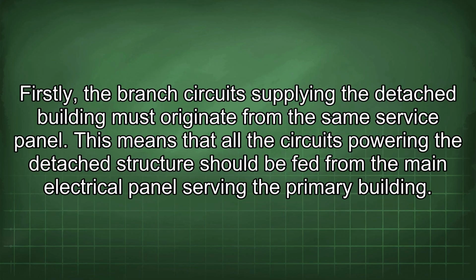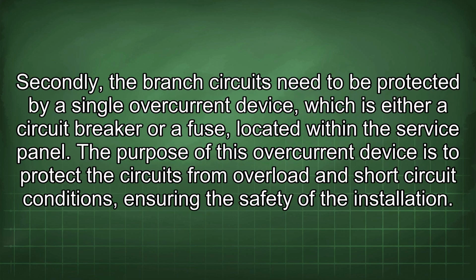Firstly, the branch circuit supplying the detached building must originate from the same service panel. This means that all the circuits powering the detached structure should be fed from the main electrical panel serving the primary building. Secondly, the branch circuits need to be protected by a single overcurrent device, which is either a circuit breaker or a fuse, located within the service panel.